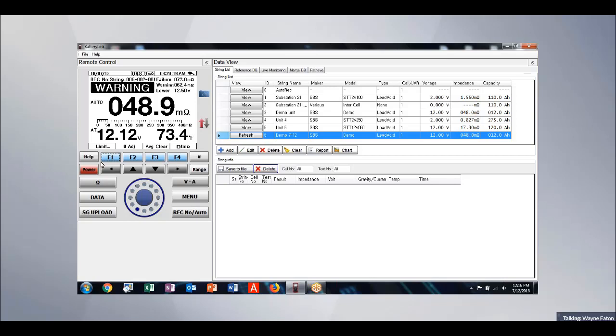And I get my voltage, I get my resistance, and I get my temperature of the negative post all within a single reading. As soon as I lift the leads off that battery, those readings stay on the screen until I connect to the next battery. When I get the audible confirmation and the pass, warning, or fail status on the screen, that lets me know I can go on to the next battery in the string and do the test on that.